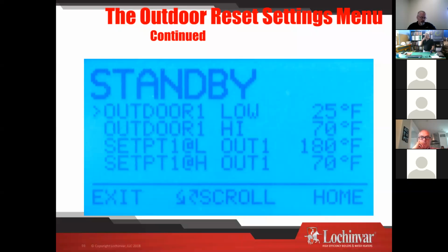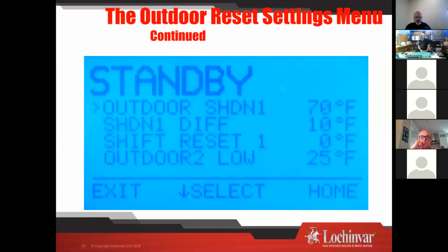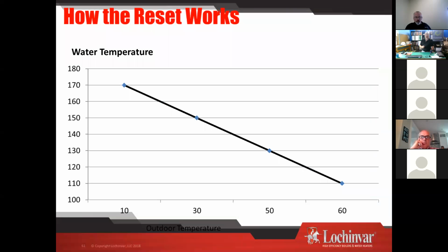So in outdoor reset, we talk about low, high, and our set points, our outdoor temperatures. So there's 5 points, but there's 4 important points. The outdoor low, that's my temperature outside, corresponds with my set point for low, and that's usually the higher water temperature. So the higher water temperature at the lower outdoor temperature, the higher outdoor temperature with the lower water temperature. Okay, so that's how those go together. And when you program them, they are going to create something that looks like this. They're literally going to create this outdoor reset curve, if you will.